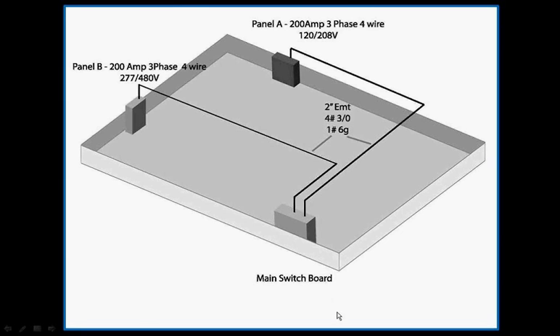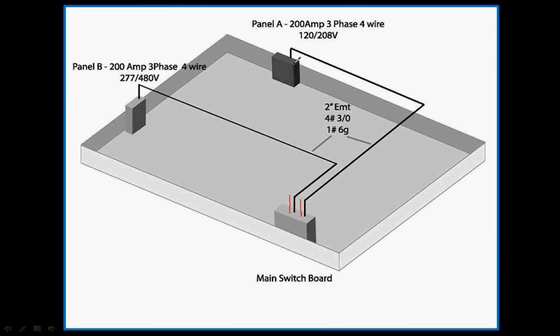First, when doing a conduit takeoff, you must include the length of the conduit risers. Now, this is an example of the conduit risers. I'll highlight them here. It's the conduit that runs out of the top of the panels. I will account for the conduit risers by over-rolling the scalex. I'll show you what I mean in just a few minutes.